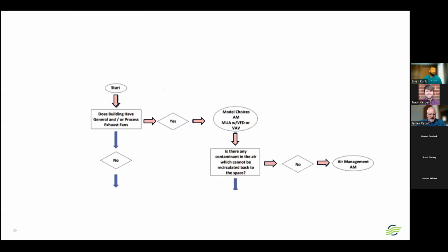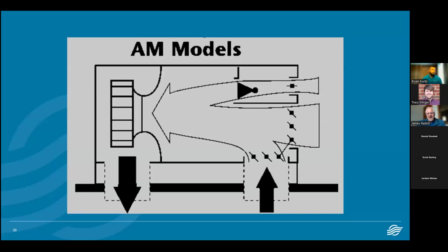So we'll go to the next screen here. And again, this is just an example. I think I should have gone to this slide when I was showing you how that decision tree works, just easier to see. This is the bread and butter, this AM model. AM stands again for air management. It uses a fan, and you can see the upper air path going over the image showing a direct fired burner. Whenever the burner's in operation, we will be supplying a minimum amount of outside air, typically 20% as needed to provide for heat and diluting the products of combustion. So we meet those ASHRAE and ANSI standards.